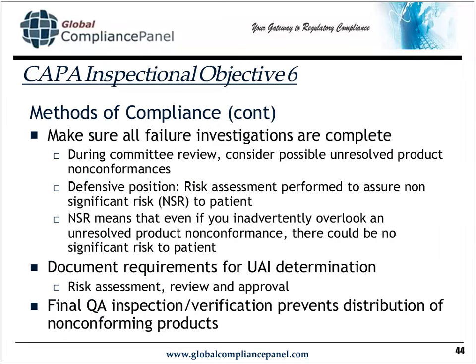Also make sure that all of your failure investigations are complete. Remember that the inspectional objective mentions possible unresolved product nonconformances. So make sure that's something during your committee, your MRB or your QRB or your complaint committee, that you surface, that as the CAPA expert at your company, you're making sure that everybody understands their responsibility to consider possible unresolved product nonconformances.